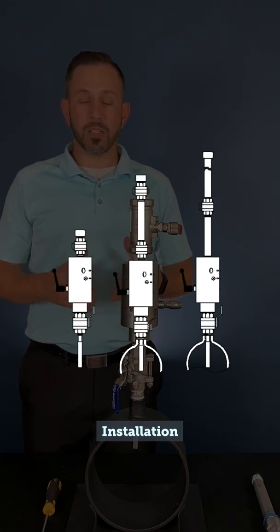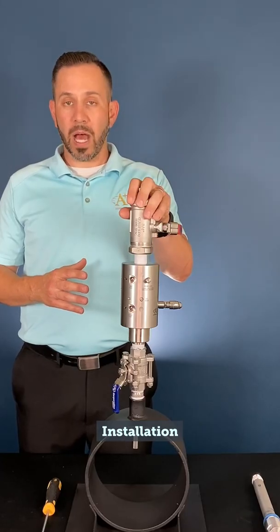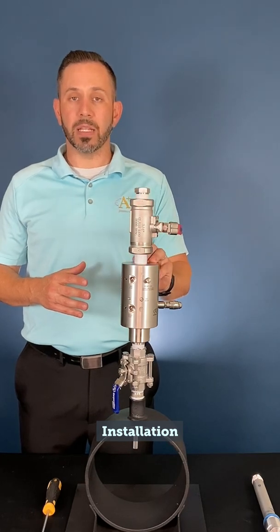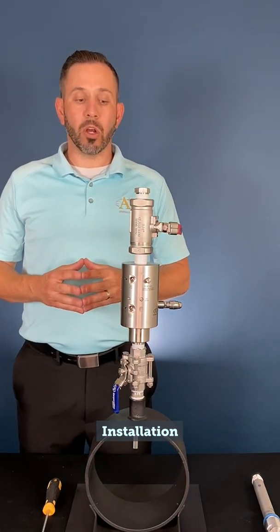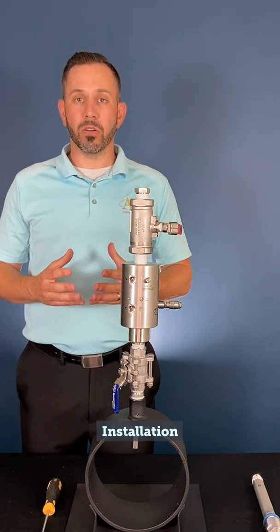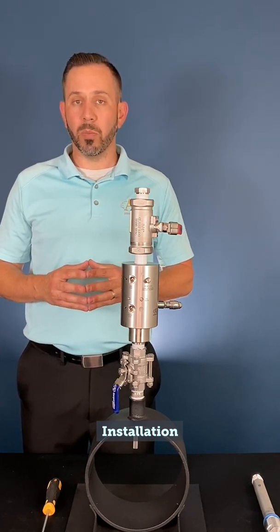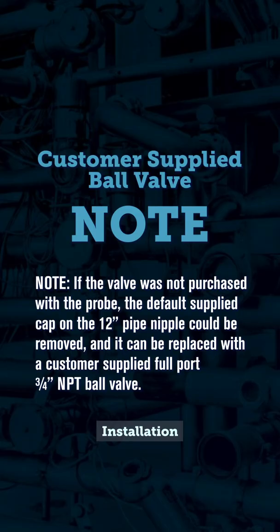If the probe is locked in full insertion and ready for use and you do not have a full-port ball valve at the top of the body, A-plus strongly encourages you to install this, as it will help if there were any errors or failures of the process seals that could inhibit you from removing the probe under pressure. Note: if the valve was not purchased with the probe, the default supply cap on the 12-inch pipe nipple could be removed and replaced with a customer-supplied full-port ¾-inch NPT ball valve.